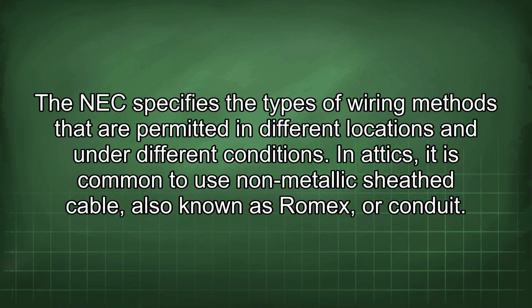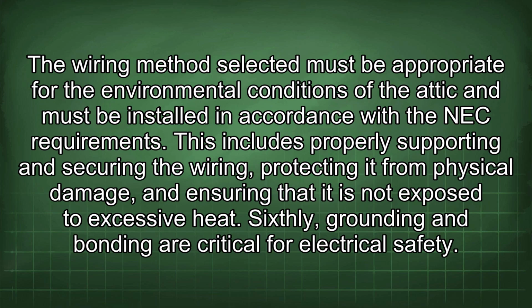In attics, it is common to use non-metallic sheathed cable, also known as Romex, or conduit. The wiring method selected must be appropriate for the environmental conditions of the attic and must be installed in accordance with NEC requirements. This includes properly supporting and securing the wiring, protecting it from physical damage, and ensuring it is not exposed to excessive heat.